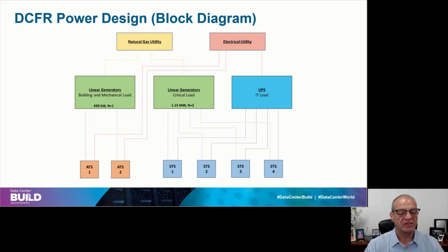And so here's what the one-line diagram looks like. I know it's an eye chart. We won't stay on it too long. But the point is that the power to the mechanical and the base loads are also serviced by both energy sources, as well as the critical load. And yes, I typically do put an optional roll-up generator connection in there, as the belt plus the suspenders at the same time. But again, they're completely flexible facilities.